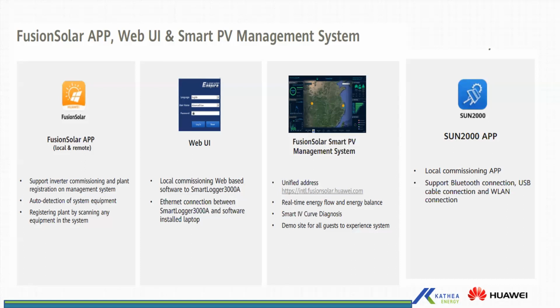The first app which they have is the Fusion Solar app. This app can actually do your local commissioning and remote monitoring as well. So with this app, you can connect to the inverter through the WLAN using the WLAN adapter or using the built-in WLAN for the lower range. And then you can set up your inverter parameters. That is the grid code, the COM address, the server addresses, and all that. And the app would auto detect all the HUAWEI equipment that are connected on the loop, making it easier for commissioning.